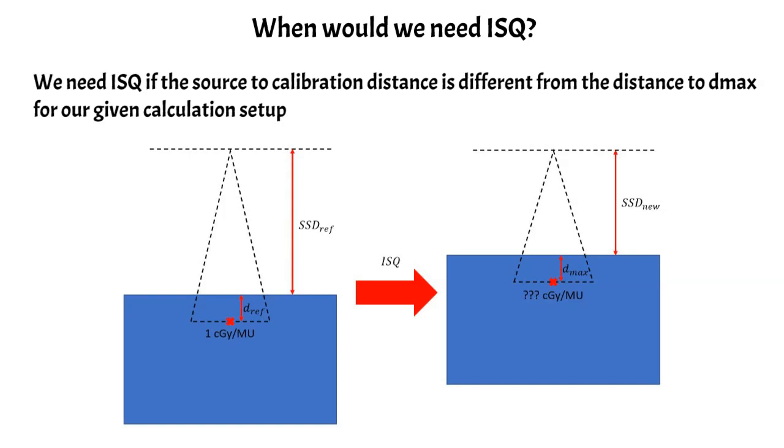So that's a little explanation showing when you might need an inverse square factor. But in most cases, if you're using the PDD formalism, you're likely to be set up to 100 centimeters SSD, which is what our PDD was measured at. So you probably wouldn't need one, but it's important to note that if you apply this formalism to other SSDs, you would need an inverse square correction. And if you're at a different SSD, you'd also need to convert your PDD to the correct SSD using the Mayneord factor because the PDD is dependent on what SSD you're at.